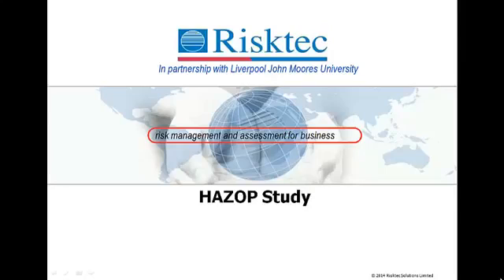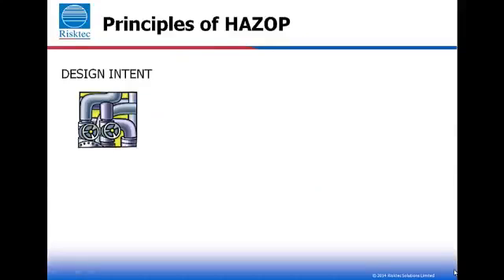In this module we will be dealing with the HAZOP method. The principle behind the HAZOP is to split the system up into a series of sections or nodes, and then for each node apply a series of guide words to identify deviations from the intended process, which will result in a hazard or operational problem.